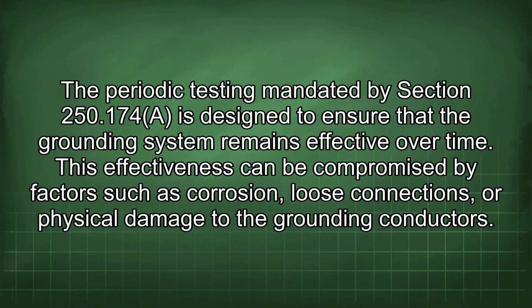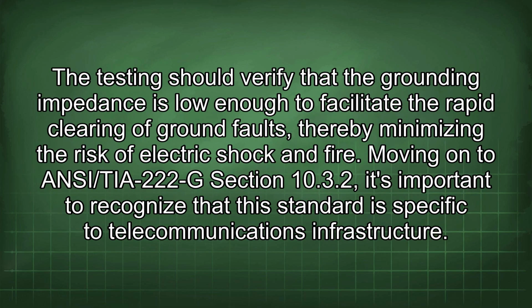In hazardous locations, the grounding of these systems is particularly important for safety. The periodic testing mandated by Section 250.174 is designed to ensure that the grounding system remains effective over time. This effectiveness can be compromised by factors such as corrosion, loose connections, or physical damage to the grounding conductors. The testing should verify that the grounding impedance is low enough to facilitate the rapid clearing of ground faults, thereby minimizing the risk of electric shock and fire.